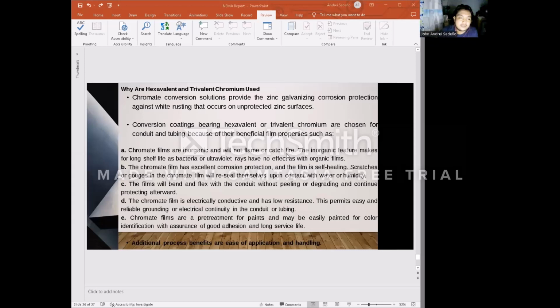against white rusting that occurs on unprotected zinc surfaces. The conversion coatings bearing hexavalent or trivalent chromium are used for conduits and tubing because of their beneficial film properties. Chromate films are inorganic and will not flame or catch fire. So hindi siya flammable. The inorganic features make for a long shelf life, as bacteria or ultraviolet rays have no effect, as they do with organic films. So mas mahaba ang life niya, like bacteria.